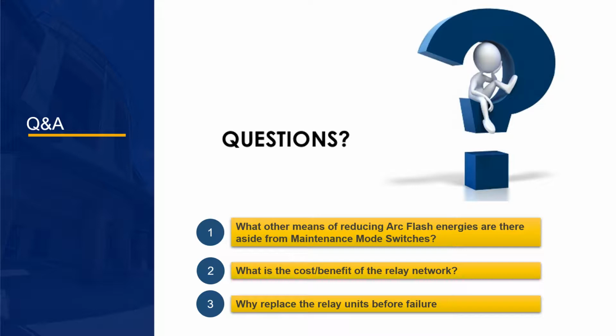With newer relays, there is always an option to include arc flash detection fiber located throughout the gear and monitored by the relays. The fiber can detect arc events before they grow and trip the breaker to clear the fault, usually faster than by detecting a fault through a CT monitoring.